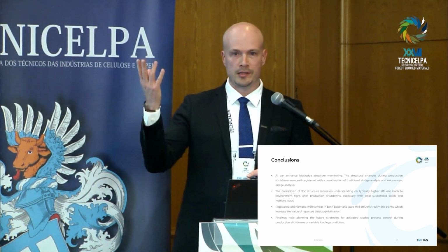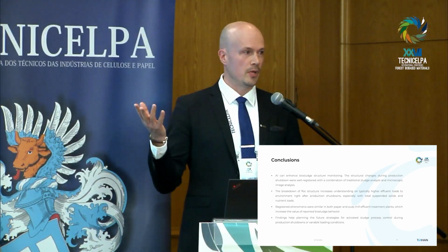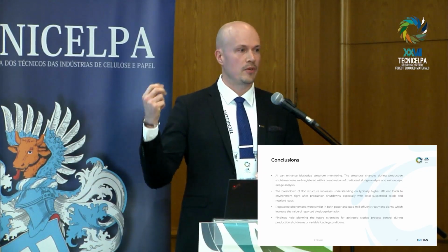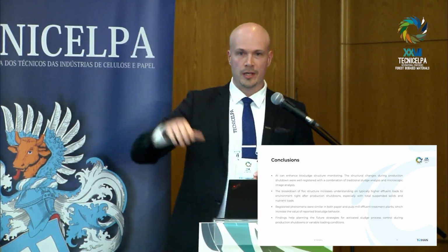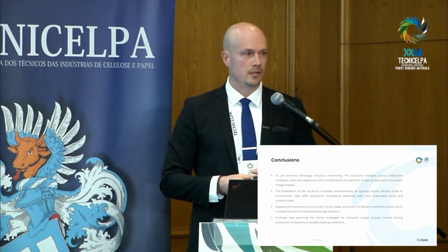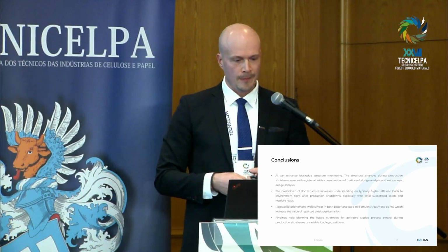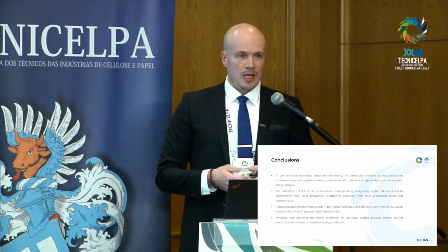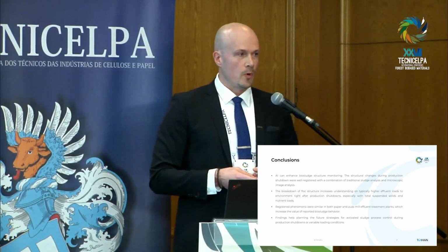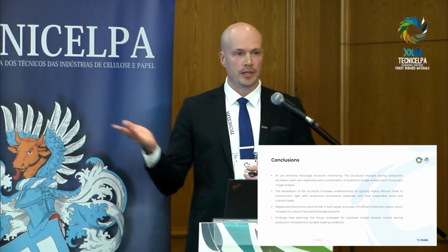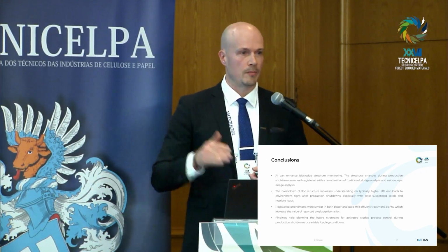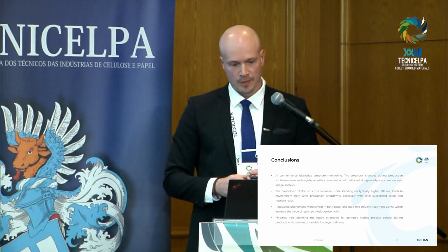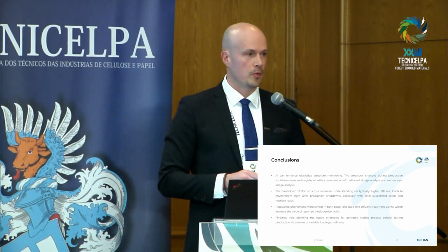Nutrients will increase their levels when the flocs decay. So every time during shutdowns, we measure an increase of nutrients in water. So even if we were growing filaments for 1 day or 2 days, they will disappear during shutdown, and we might have an opportunity to reduce the nutrient load to the environment.